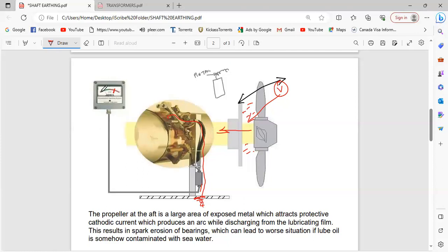It should not be zero for the simple reason that your lube oil is acting as an insulation, and it should not be zero whenever your ship is in motion, because there will be sufficient lubrication oil here and sufficient lubrication over here, and due to the proper earthing, this charge is definitely going to be going down to ground, giving a minimum voltage reading over here. Okay, and that minimum voltage reading should be anything between this green portion. Okay, if it is showing zero during your particular running, okay, we'll see that now.